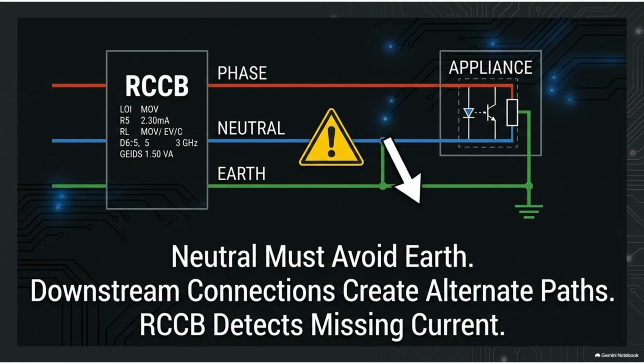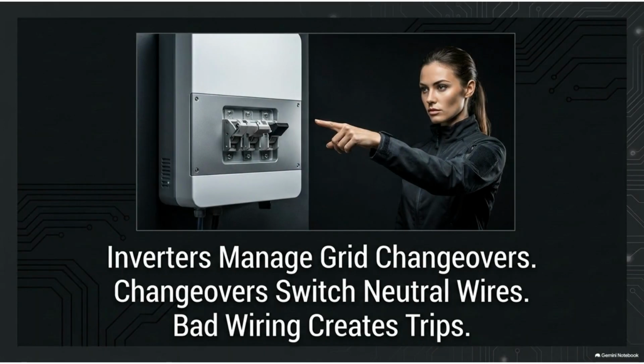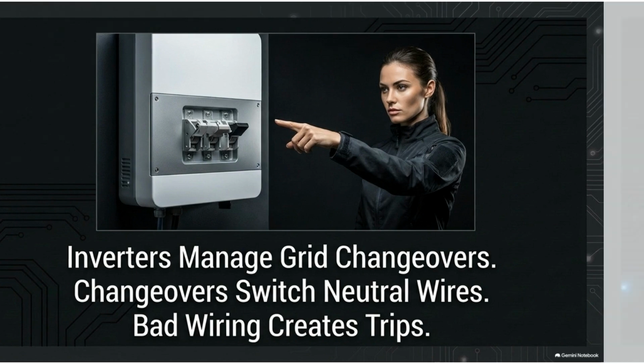The neutral line must remain isolated from the earth. Downstream wiring errors that create alternate paths for current will cause the RCCB to detect a missing current and trip. Inverters are used to manage grid changeovers, often switching neutral wires. If the wiring for this system is incorrect, it can easily lead to nuisance tripping of your RCCB.